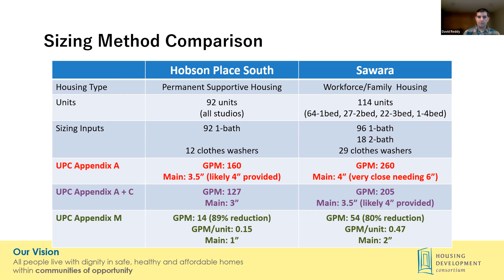The UPC Appendix M, which we're recommending and is in the code, the 2018 plumbing code, would result in an 80 to 90% reduction in that peak GPM estimate, which is dramatic in terms of pipe sizing. The main size required for these two buildings goes down 2 or 3 sizes here, depending on the utility's increment. So this is a dramatic reduction, and I'll show later that it can save a lot of money.